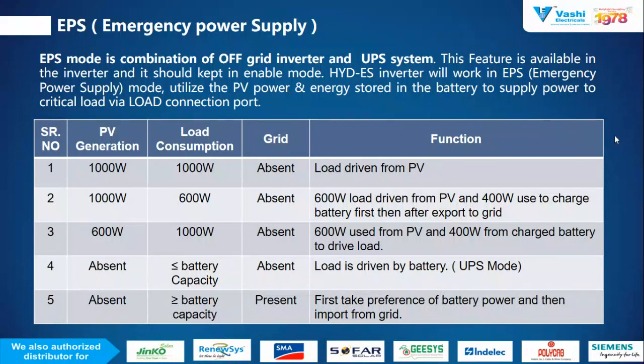Now consider the third point, which is the reverse of the second. Your PV generation is 600 watt and load consumption is 1000 watt. In that condition, if the grid is absent, 600 watt is used from the PV and 400 watt from the charged battery. Since the battery was charged during the daytime, 400 watt is used from the battery to drive the load. Fourth condition, where PV power is absent, meaning your solar power is absent, your load consumption is less than or equal to battery capacity, and your grid is absent. In this condition, the load is driven by the battery.